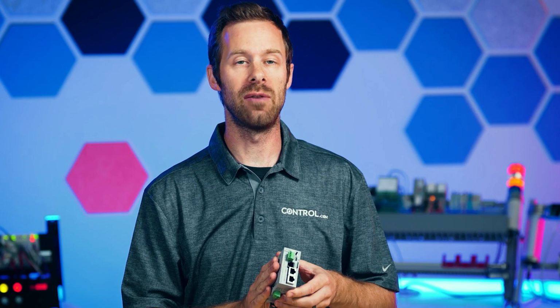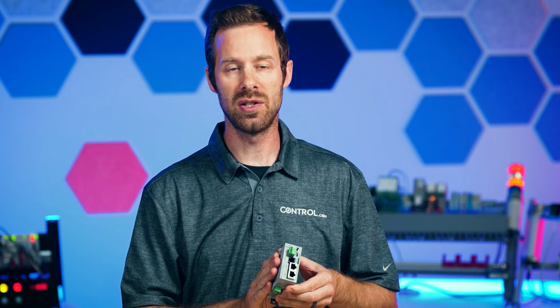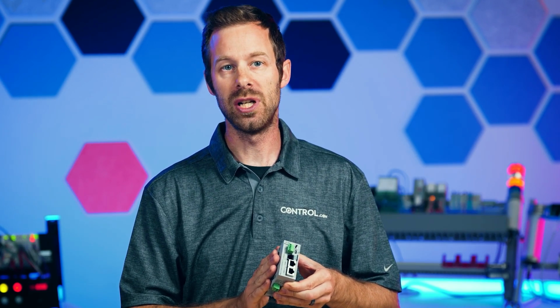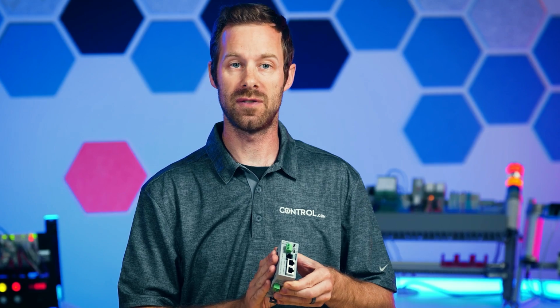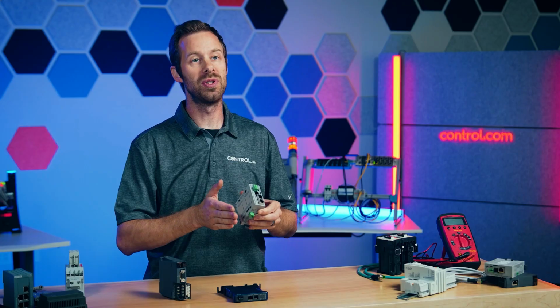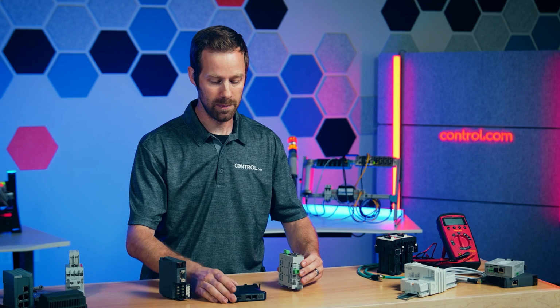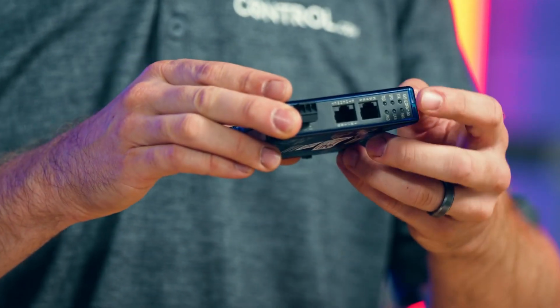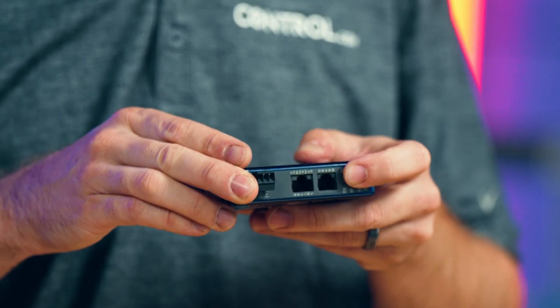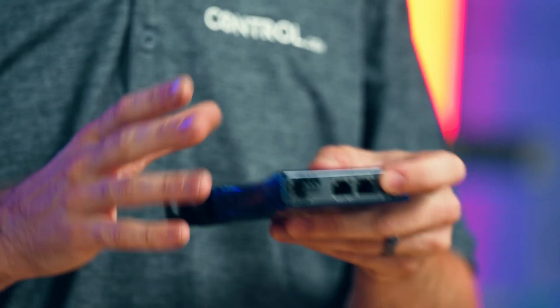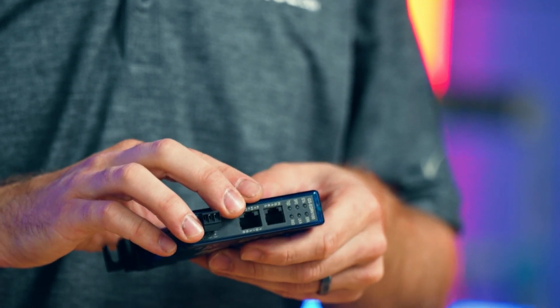In RS-485, we refer to these as nodes. These nodes will have addresses. For each specific variation of RS-485, the standard will determine how many nodes are available for each system. What we can do with these ones is send over communication protocols such as Modbus. That's a very common one to be used over RS-485.